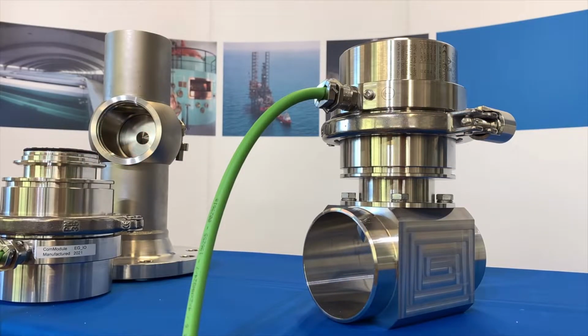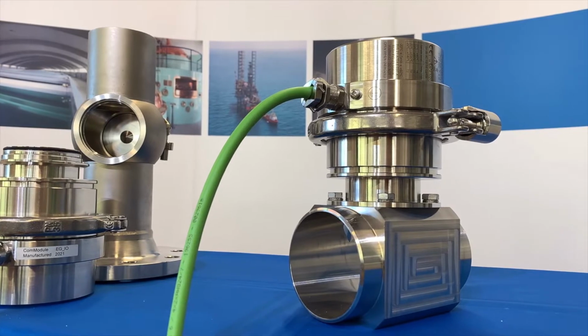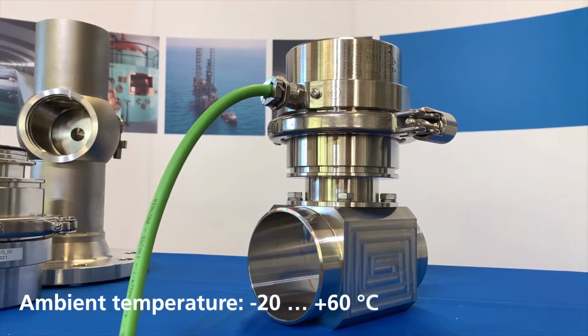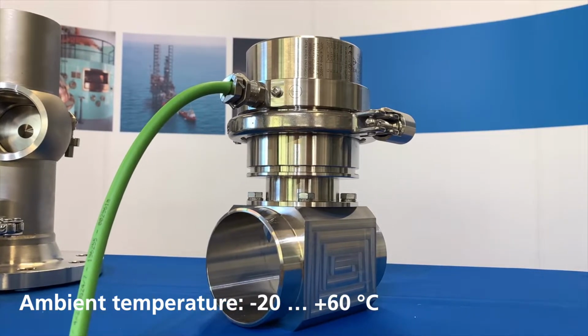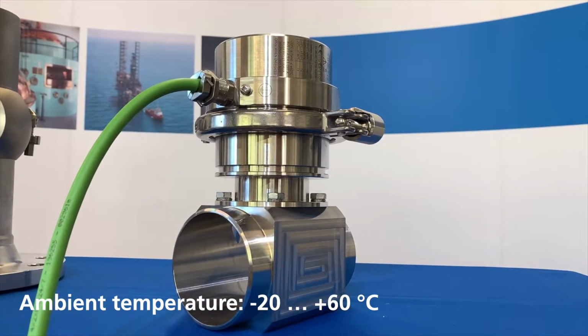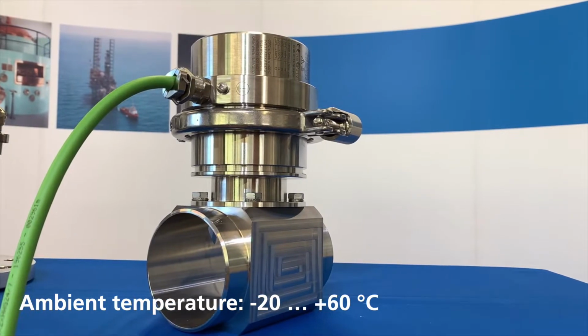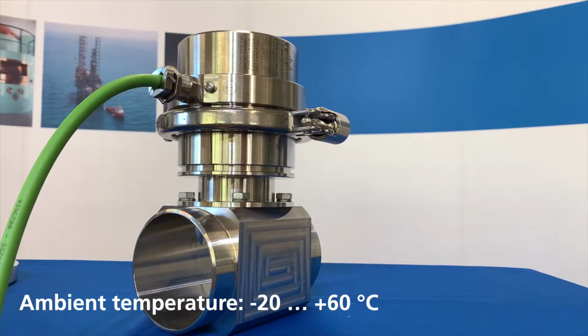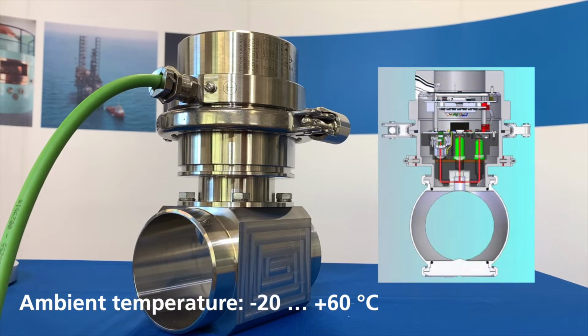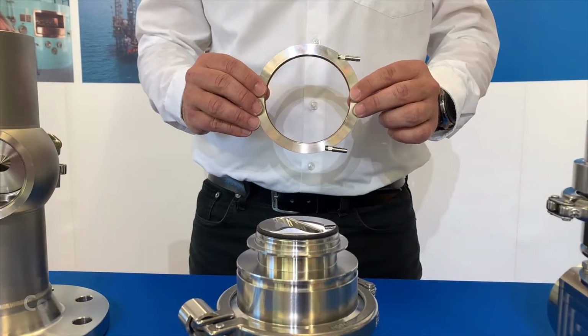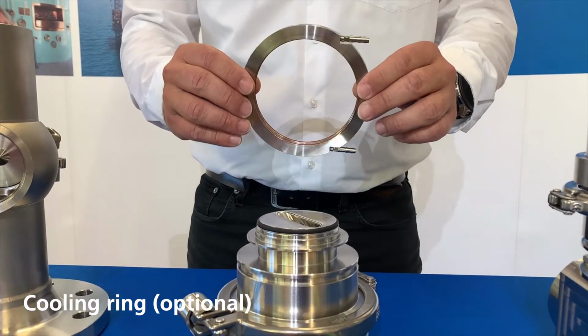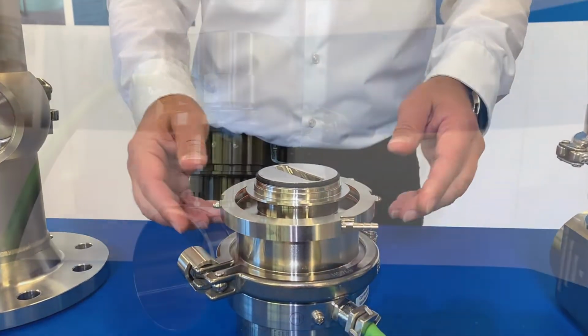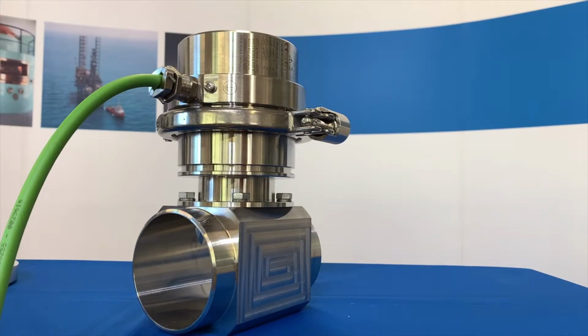Another difference to the DualScat X is the ambient temperature. We now allow an ambient temperature of 60 degrees. With the DualScat X, the maximum was 50, which limited our possibility in certain projects in the past. A unit is built in such a way that a thermal separation has been installed between the medium and the electronics. This separator protects the electronics from excessive temperatures. Where necessary, an optional cooling ring can also be used in order to offer our customers a solution also for higher ambient and medium temperatures.